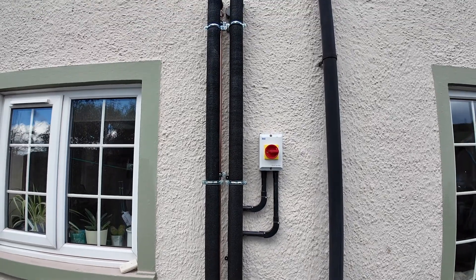On the last video we posted, a few people commented that they prefer to see primary pipework inside trunking. On our first few jobs we actually did use trunking, but since we started using the Primary Pro we've realised it gives a better finish. With trunking it's quite difficult to get the pipes inside with the right level of insulation, and it's actually impossible to get it in there with the pipes clipped over the top of the insulation as they should be. That's the end of day one — just in time too as it started to rain — so it's off to find the hotel, get some food and rest ahead of another big day tomorrow.